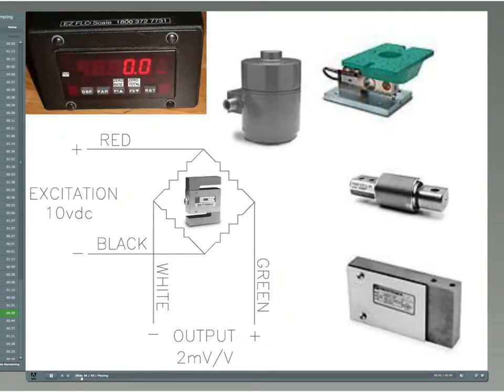The scale indicator supplies excitation voltage to the load cell, and in turn, the load cell supplies a signal voltage to the indicator in proportion to the weight applied to it. The diagram shows a 4-wire load cell. The load cell has 2 input wires and 2 output wires. The load cell has a full-scale load rating and a full-scale output sensitivity rating.